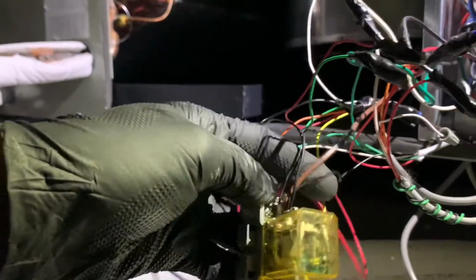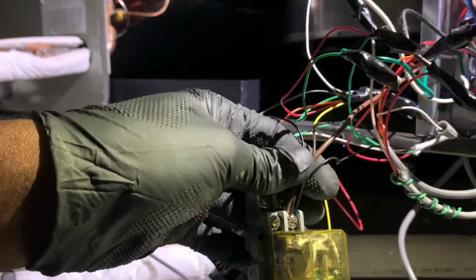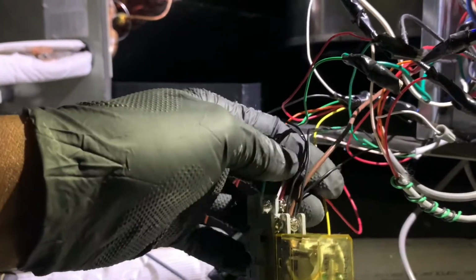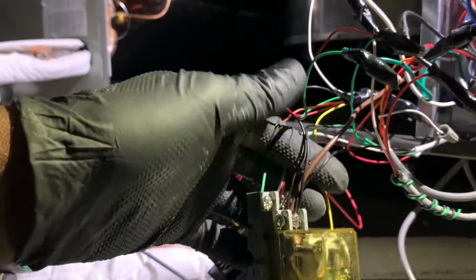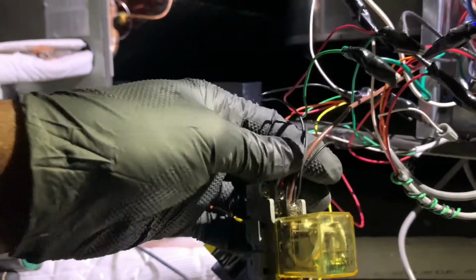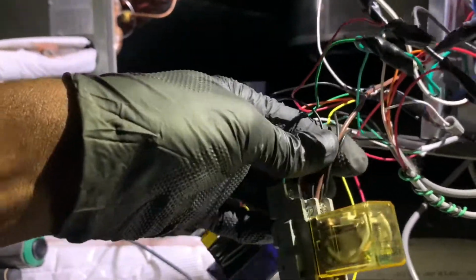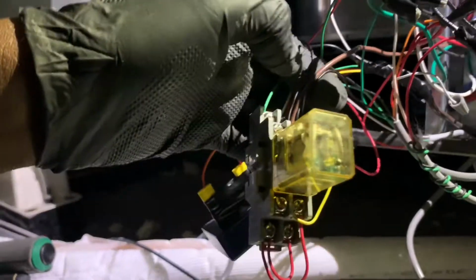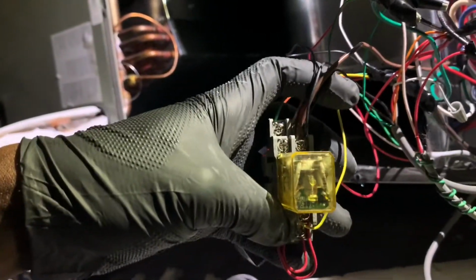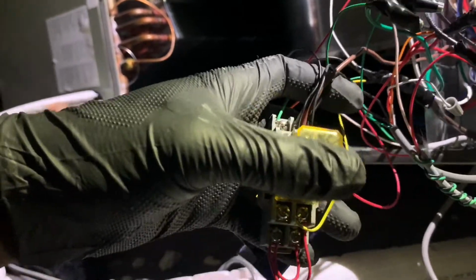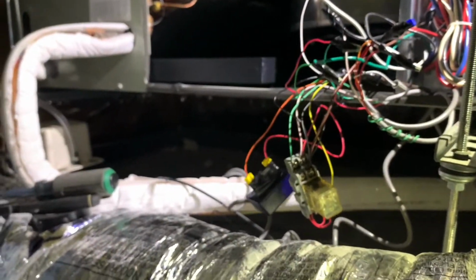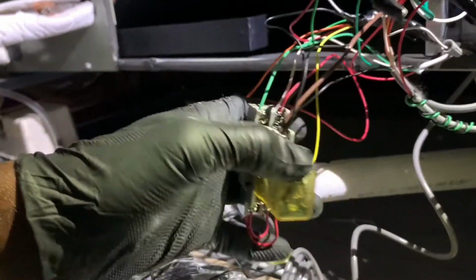So all this right here is common for my wet switch or my flood detector, common for my outdoor condenser, common for my thermostat, and it's supposed to be common for this relay. So I've got to move this group of wires, put it right here. So that was a simple mistake. I saw this right now as I'm going over it, because this is real time. So I just wired it up and thought I'd do a video. So this is real time. So I'm just going to make that simple correction.